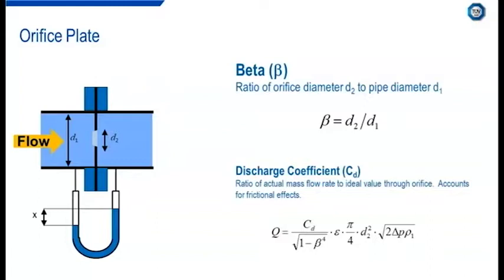The mass flow through the differential pressure meter can then be calculated from the differential pressure measured through the meter, knowing the fluid's density and the beta ratio. The governing equations that are appropriate for differential pressure meters are well documented, as well as the limits of use in the standards available. The discharge coefficient, CD, accounts for frictional effects and has again been well characterised for each DP meter available through years of research and development. Differential pressure meters such as the Orifice Plate can generally be used without flow calibration, which is one of the main advantages.